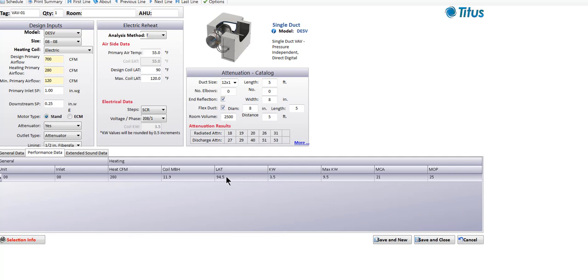You can also see that it gave us an electrical schedule — the MCA and the MOP. MCA stands for minimum circuit ampacity, meaning everything in the circuit supplying this unit has to be rated for 21 amps or more. It also says the maximum overcurrent protection is 25, meaning the maximum recommended circuit breaker for this unit would be 25 amps.